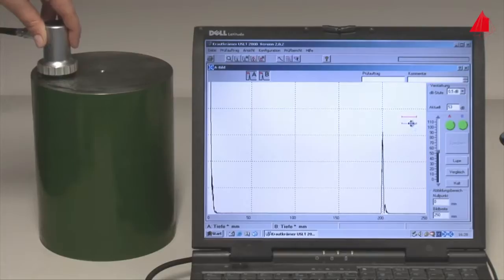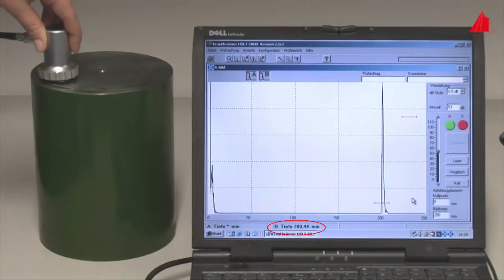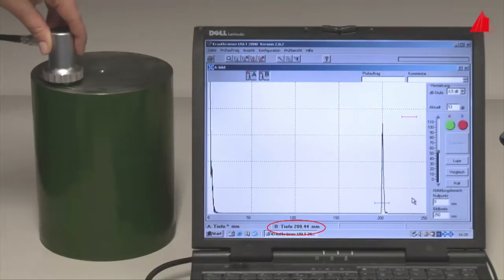With the help of so-called trigger gates, which may be set on the echoes with a computer mouse, the depth of the defects can easily be read off at the lower left-hand corner of the monitor. The cylinder back wall lies in a depth of about 200 millimeters below the probe, so the cylinder has a height of 200 millimeters.